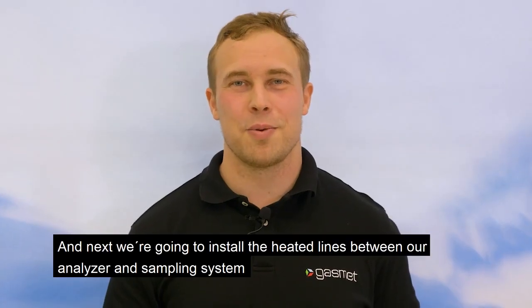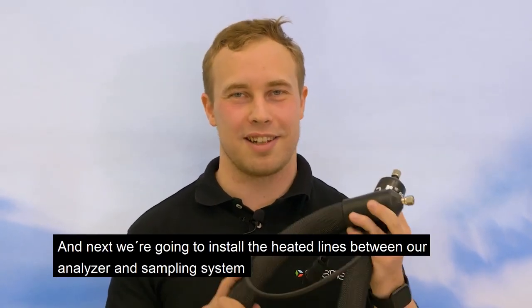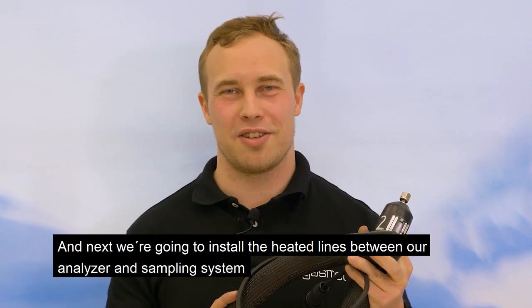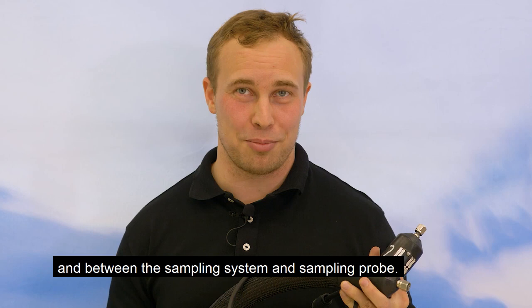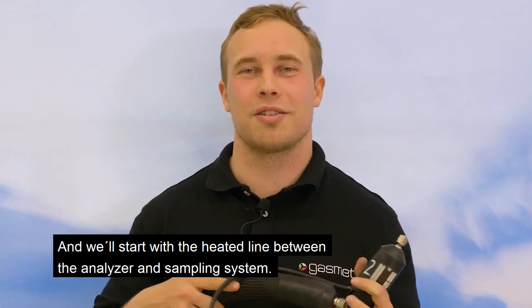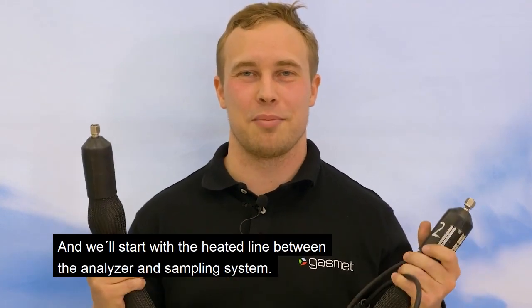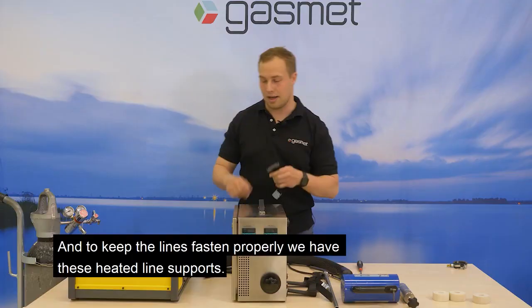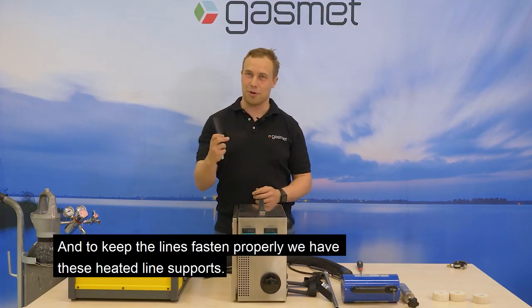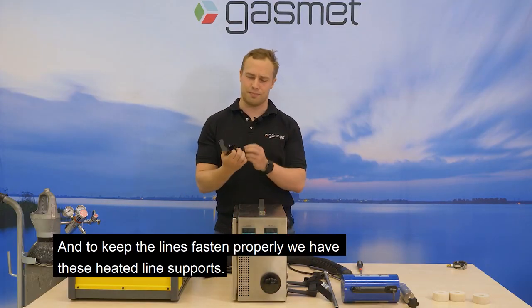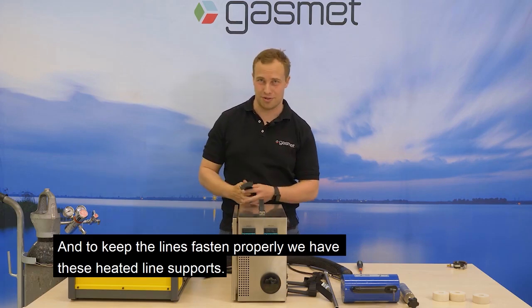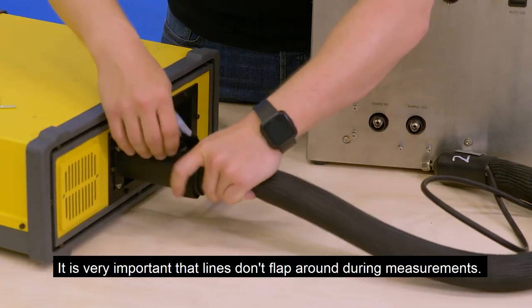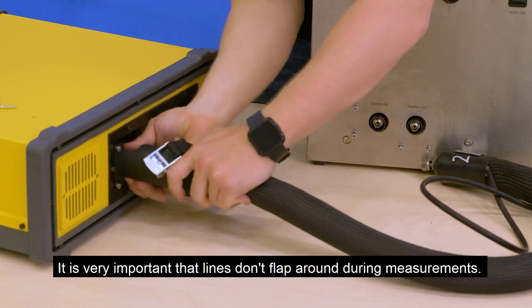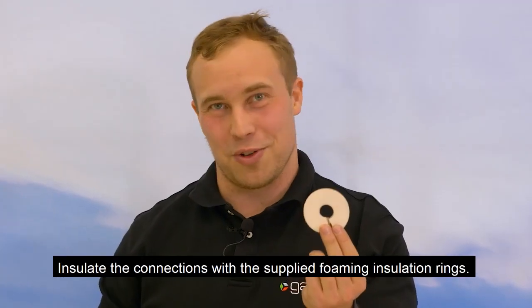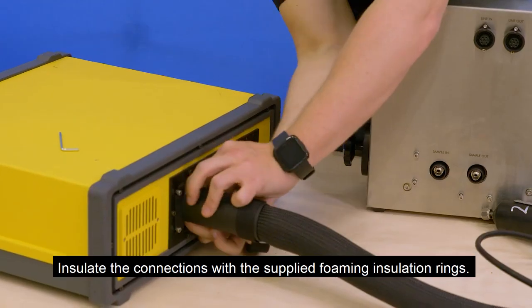And next we're going to install the heated lines between our analyzer and our sampling system, and between the sampling system and the sampling probe. And we'll start with the heated line between the analyzer and sampling system. And to keep the lines fastened properly, we have these heated line supports. You see, it is very important that the lines don't flap around when doing measurements. Insulate the connection with the supplied foam insulation rings.